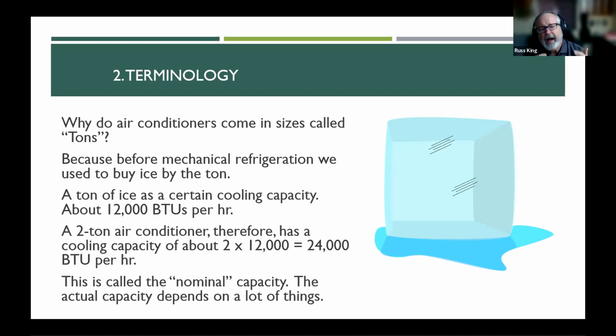So 12,000 BTUs per hour is the nominal cooling capacity of a ton. So when a manufacturer makes an air conditioner, they shoot for those increments of 12,000 BTUs. They do it in half tons too. So you've got typically 1.5, 2, 2.5, 3, 3.5, 4, and then 5-ton units. A 2-ton unit, 2 times 12,000, is going to be around 24,000 BTUs cooling capacity. So that's basically what a ton is, 12,000. You can actually go look at your condenser, and after you get used to reading model numbers, you can determine the tonnage from the model number. There'll be numbers like 024 and 048. You divide that by 12 and get the tonnage, okay?